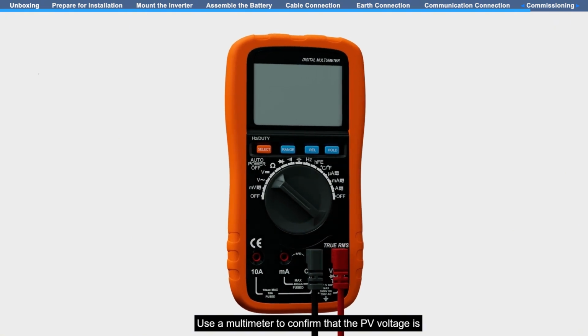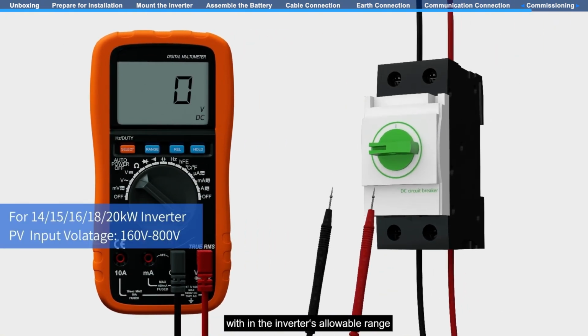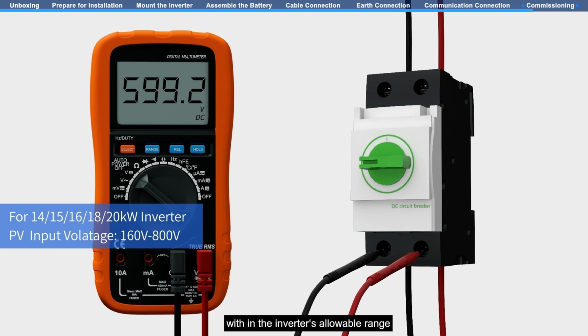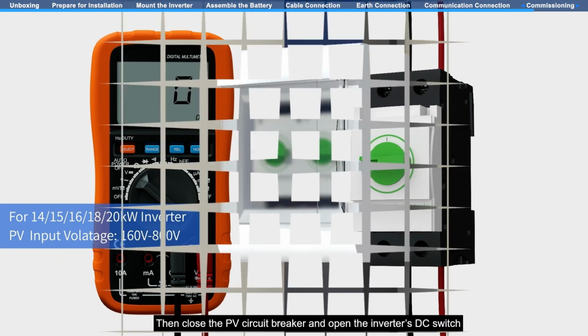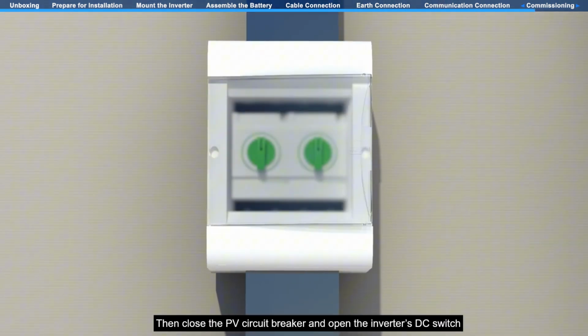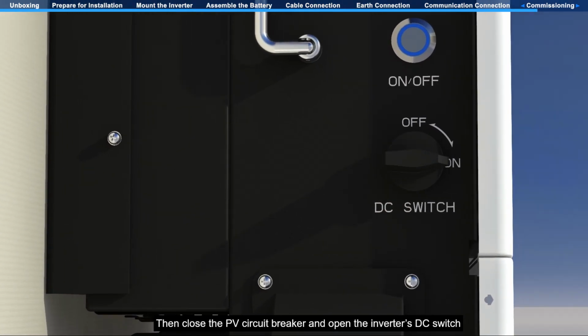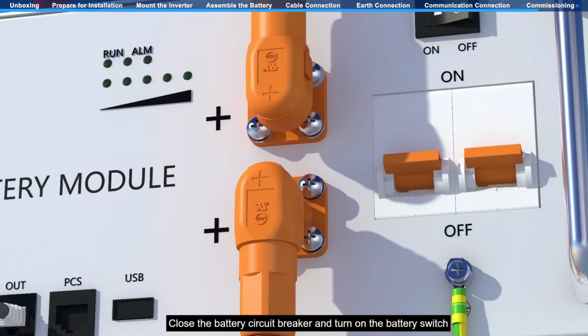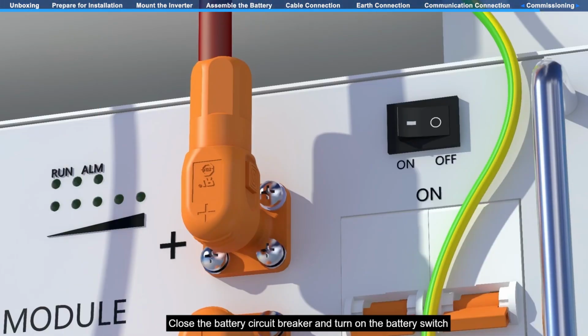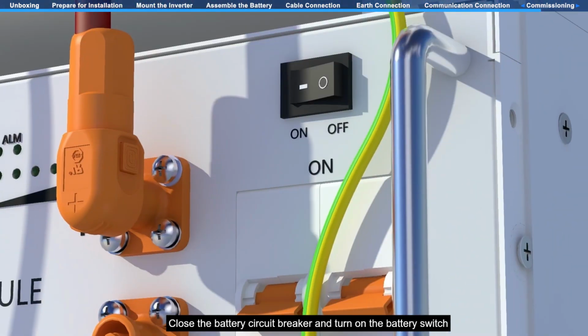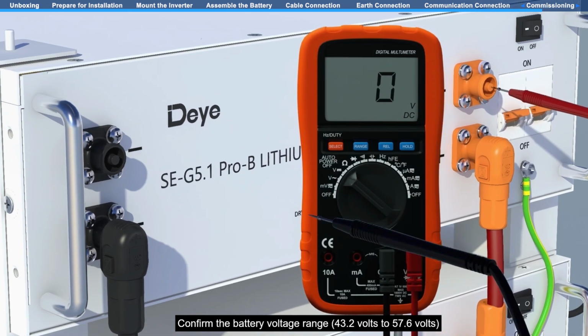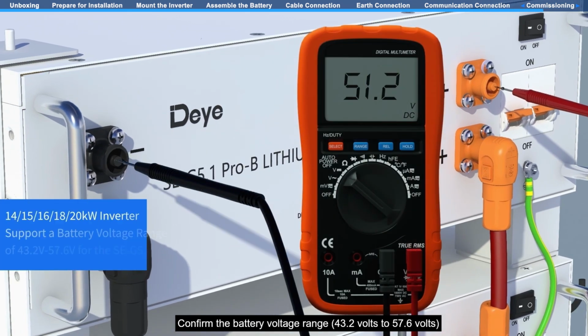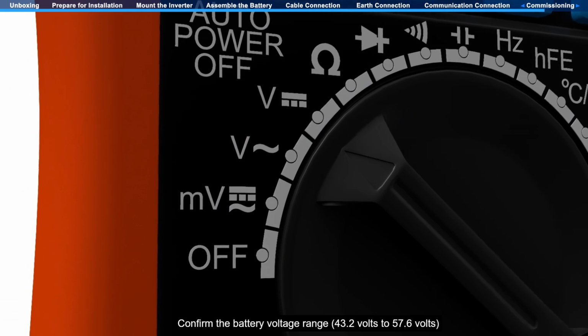Power on and commissioning. Use a multimeter to confirm that the PV voltage is within the inverter's allowable range. Then close the PV circuit breaker and open the inverter's DC switch. Close the battery circuit breaker and turn on the battery switch. Confirm the battery voltage range, 43.2 volts to 57.6 volts.